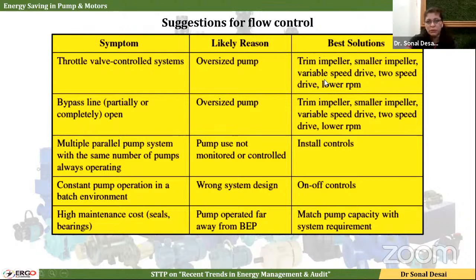Same way, go with a VFD or a variable speed drive. That will also reduce the speed. Also, you can opt for a 2-speed drive, high speed when required for more flow rate, or a low speed when you are running at low flow, or reduce the RPM. So by any possible way, you can increase the efficiency and eradicate this throttle control system. The second kind of arrangement is when there is a bypass line used. As just said, flow is diverted from the main line. So the same remedy is applicable as in the first case.